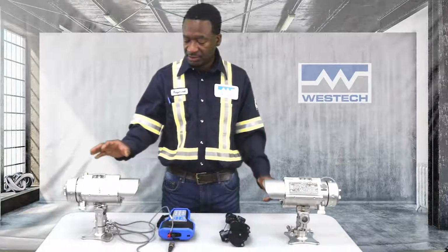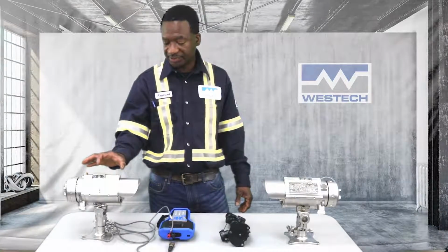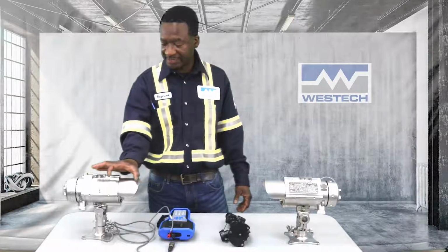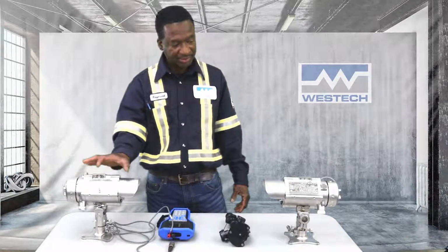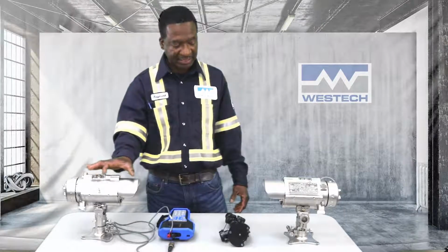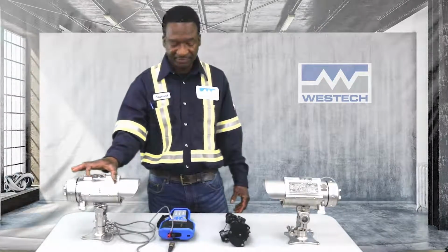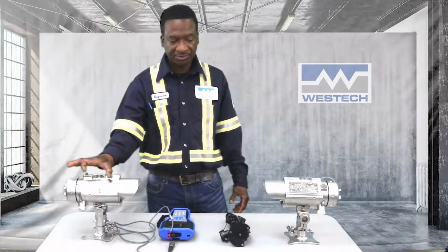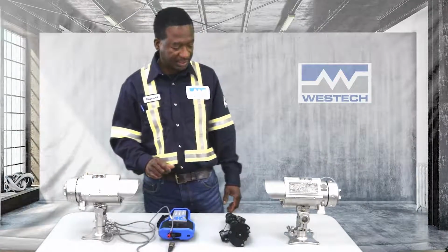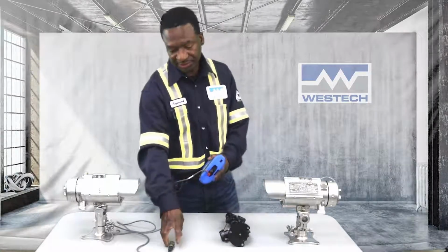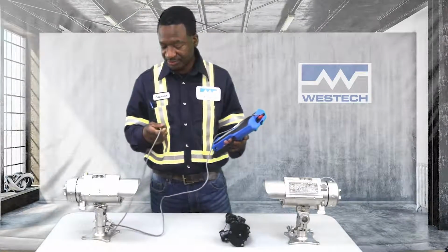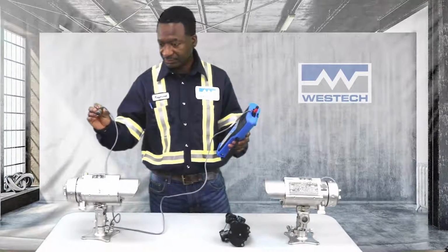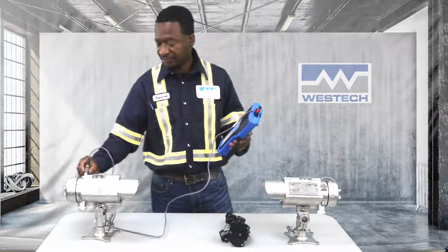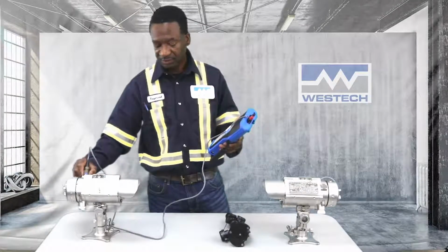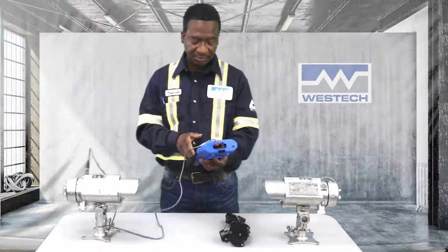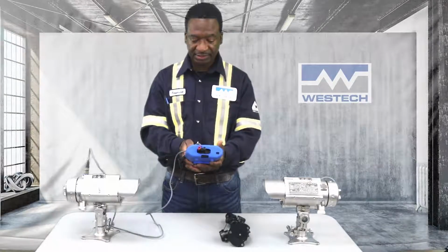To do the zero, you can do it three or four ways actually. You can use the supplied magnet in the kit and swipe it along the sides of the receiver three times. So you put the detection system in alignment mode, standby mode, and then a zero is done. You can use the HART communicator as well, or a Trex, and it comes with a specialized cable, and you fit the cable onto the receiver, and in maintenance mode, you dial into the system and select zero calibration.